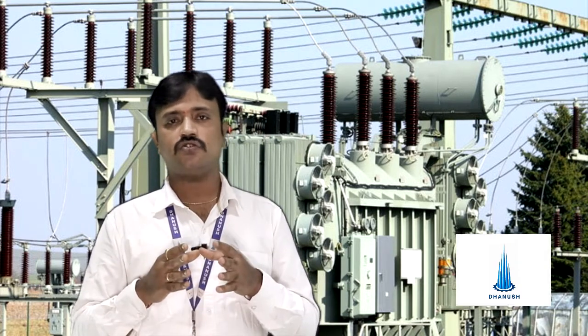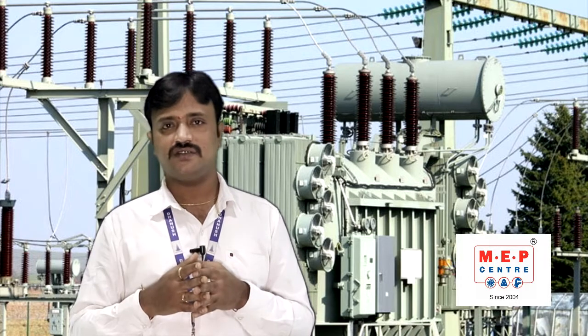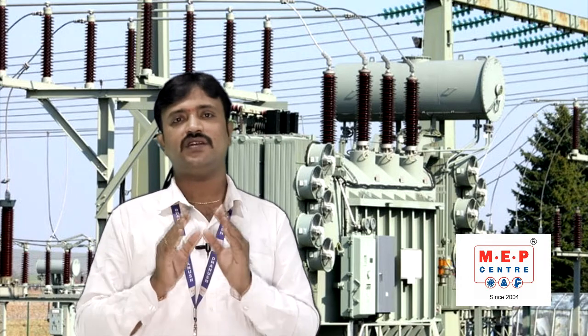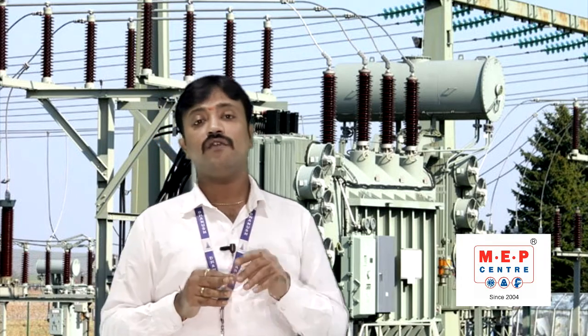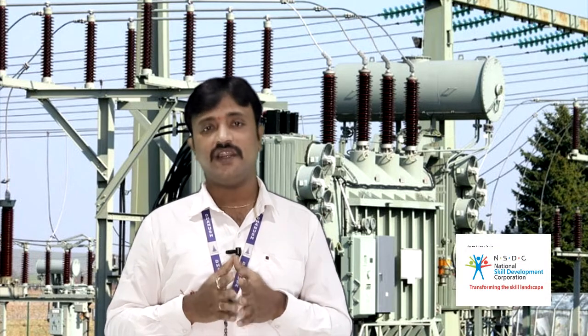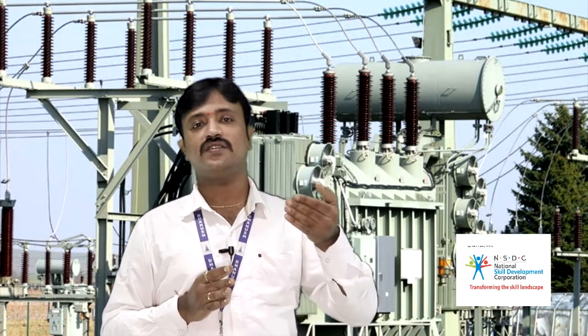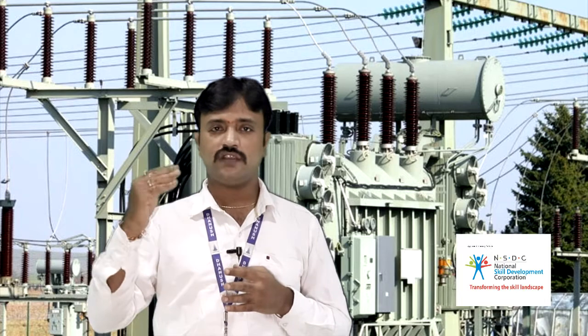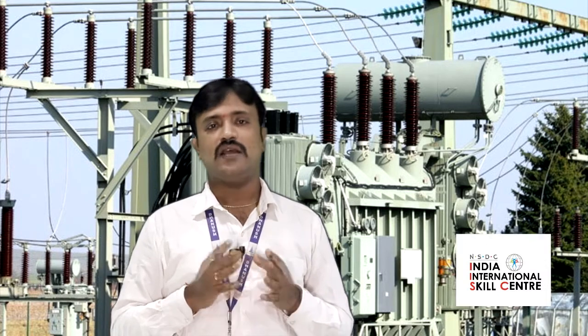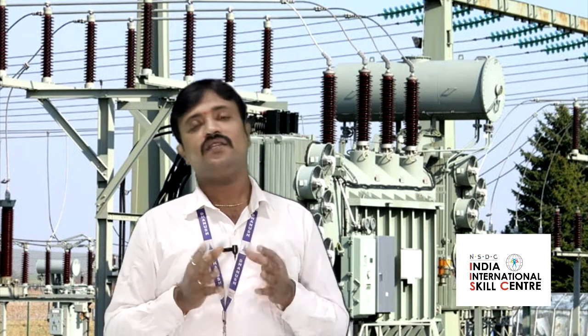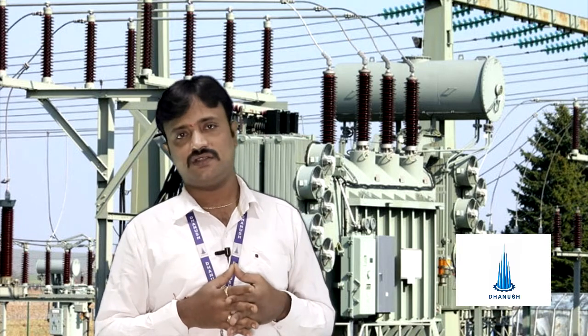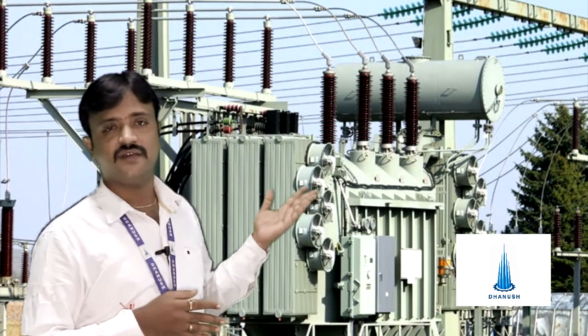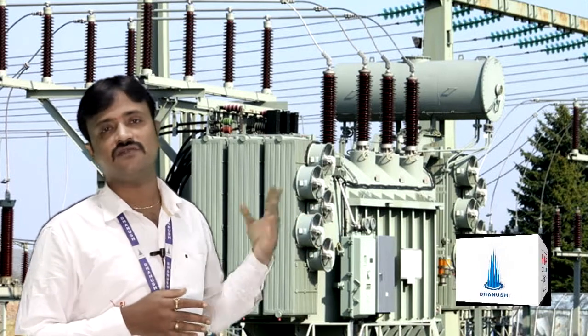See, the transformer is not something we change on a regular basis. Once it is proposed, it is final. So whenever you are defining the transformer size for any type of building, we need to consider the MDB load, plus we need to take some future expansion loads also, as well as the demand factor and diversity factor for the building. And then we propose the transformer size, okay? Like 630 kVA is there, 1000 kVA is there, how much transformer size we require, that we are going to calculate.